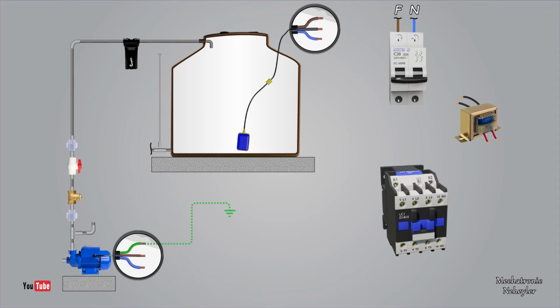Therefore, one of the most appropriate solutions for this case is to use a contactor, which separates the maneuvering or control circuit from the power circuit. To do this, a contactor with a 24-volt coil must be used, which allows the control part to be separated from the power part. And to go down to that voltage that the contactor coil needs, a transformer with a reduction to 24 volts must be used. So, with these 2 additional components, we can now make a secure connection.